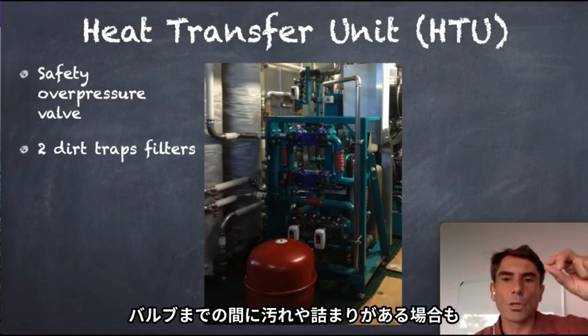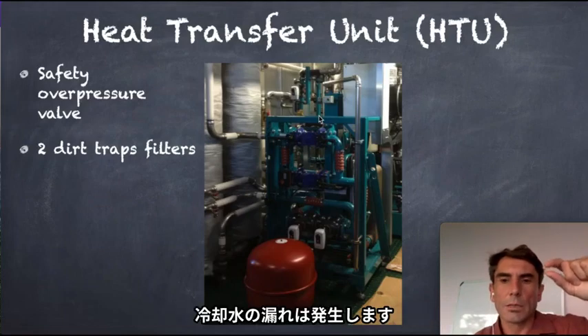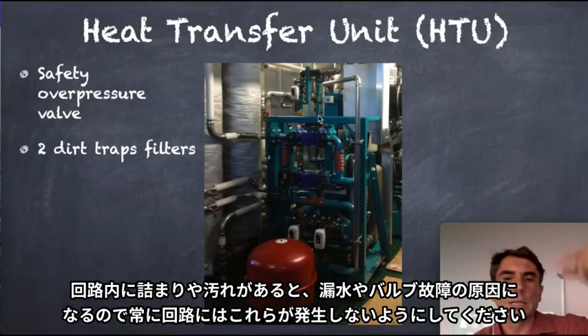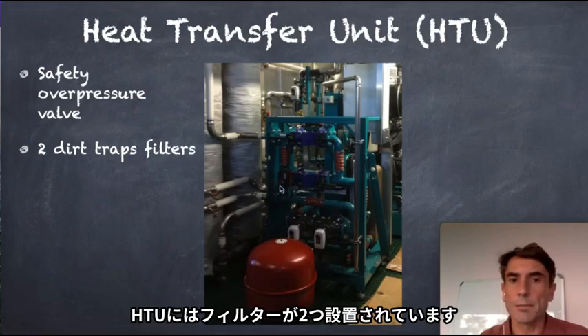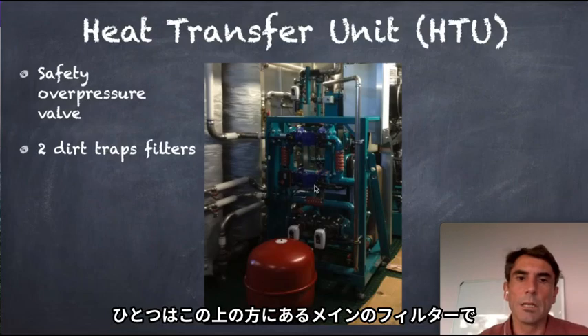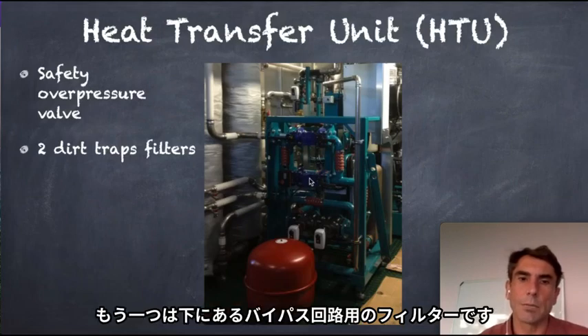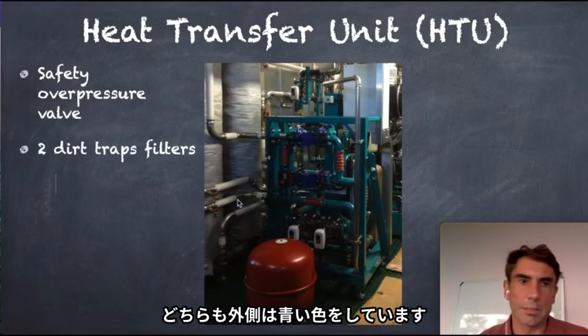So if there is dirt in between the valve and the closing point, so if there is dirt or whatever in between, then it could start to leak through that valve as well. So then we have to either flush it quickly so that we get the dirt out between the seals, or the valve by itself has some problems of leaking. So we have two dirt trap filters on the HTU. We have one, the mainline filter, and we have a bypass filter, the second one here. These are the two blue items here.